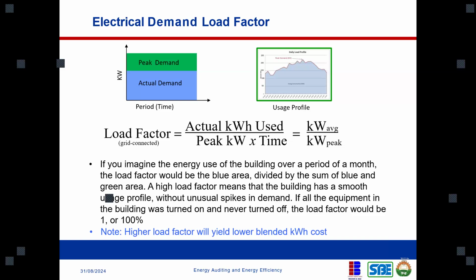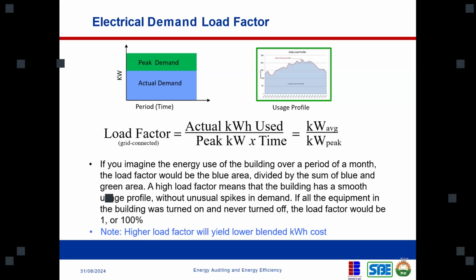So assuming you have a generator, now this is for grid connected. Okay, but let me bring it in the context of a generator. If you have a generator that is maybe 100 kilowatt, 100 kilowatts essentially might be like 120 kVA, right? But let's say 100 kilowatt. And you put a load of, let me say, 80 kilowatt on that generator. For every time that generator is working, you have a load of 80 kilowatt. Then what that means is that the load factor on that generator is actually 80%. Okay, it's actually 80%. I'm just using this illustration to make it simple, assuming that that load remains 80 constantly. But if the generator has a capacity to produce 100 kilowatt and you're using 30 kilowatt, for example, then what that means is that the load factor of that generator is 30%.